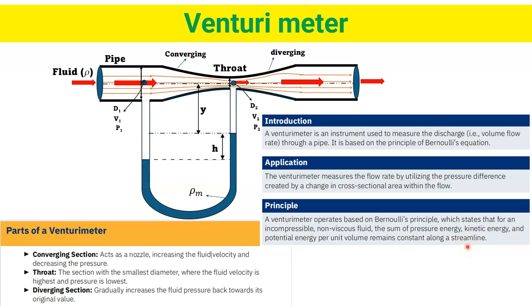A Venturimeter has three parts. First is the converging section, which acts as a nozzle, increasing fluid velocity and decreasing the pressure. Next is the throat — the section with the smallest diameter where the fluid velocity is highest and pressure is lowest. Then the diverging section gradually increases the fluid pressure back towards its original value.